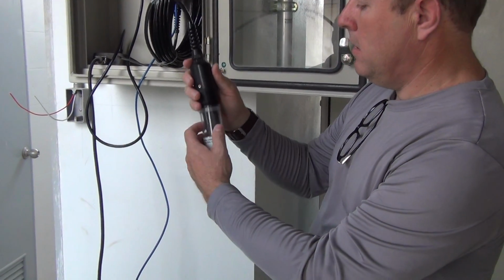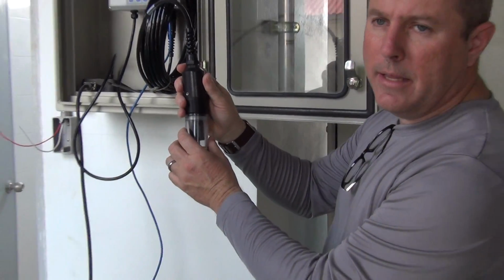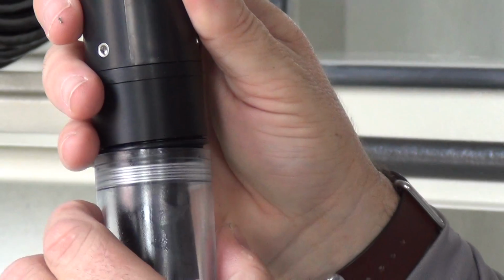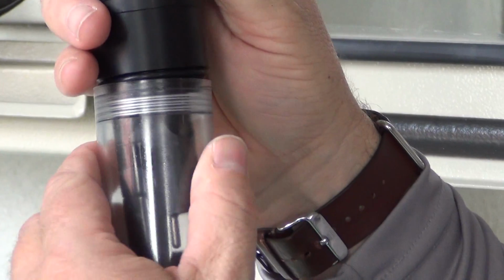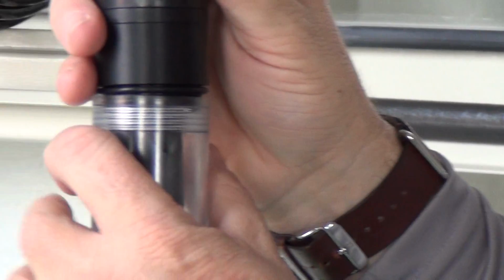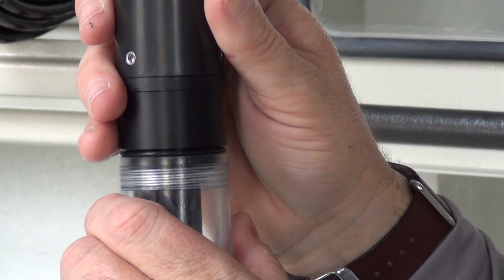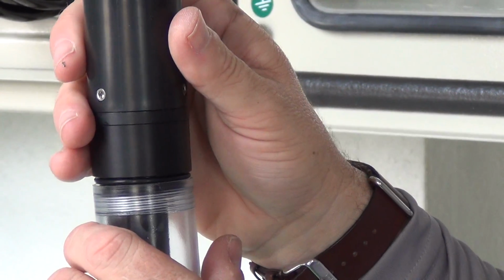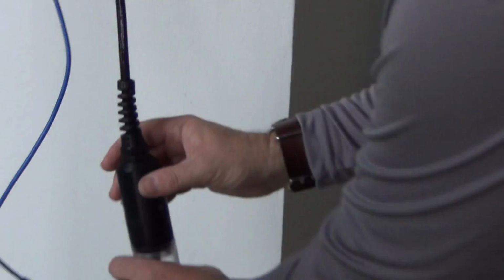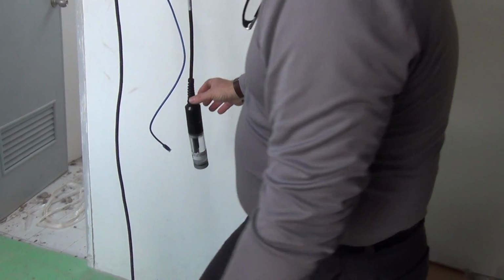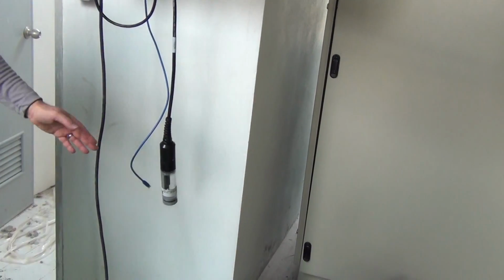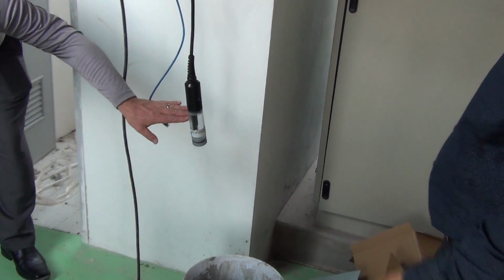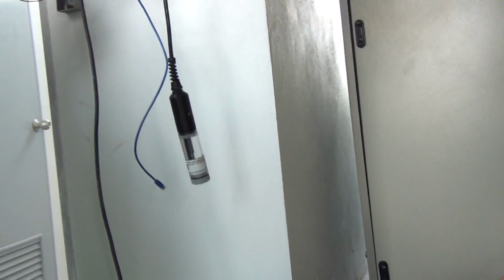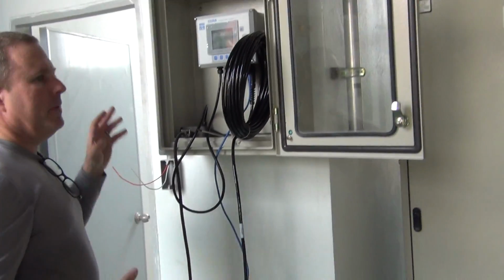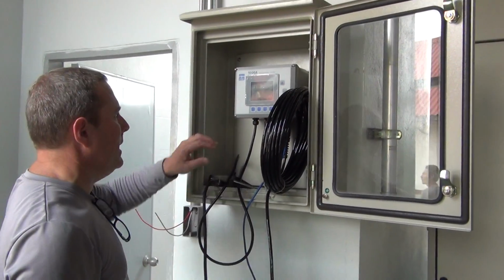I insert, and I'm not going to tighten this. I need it to be able to measure atmospheric pressure. So what I do is I'm just getting it to where it hangs on a thread. Very loose. Carefully just set it down. I look at it, I make sure that the water is not in contact with anything. It's just in there, and it's going to measure the amount of dissolved oxygen in that space.